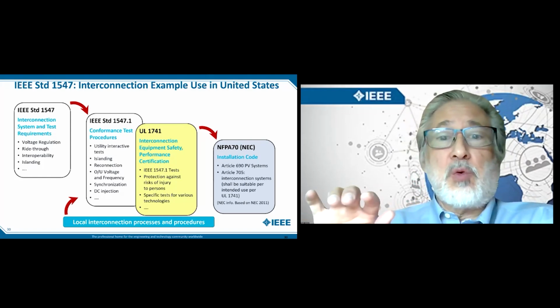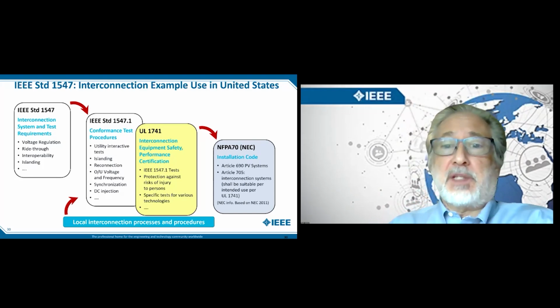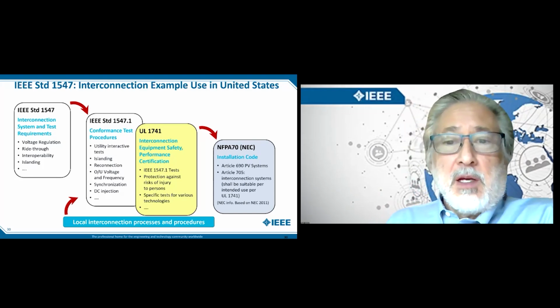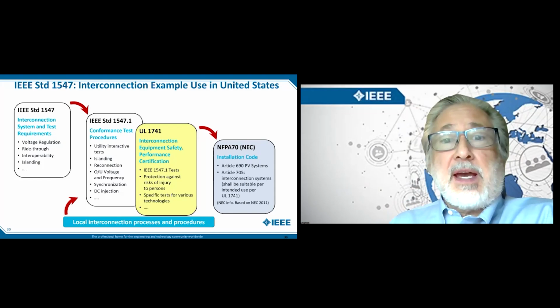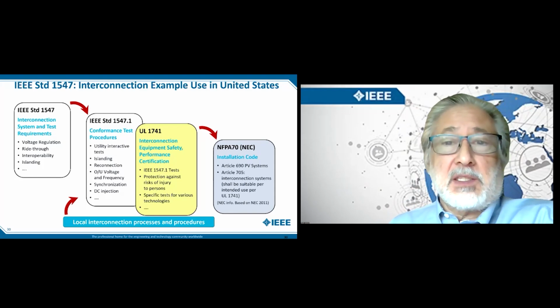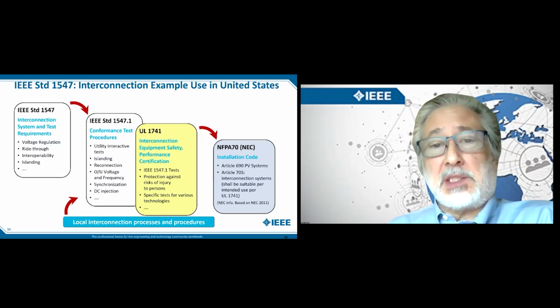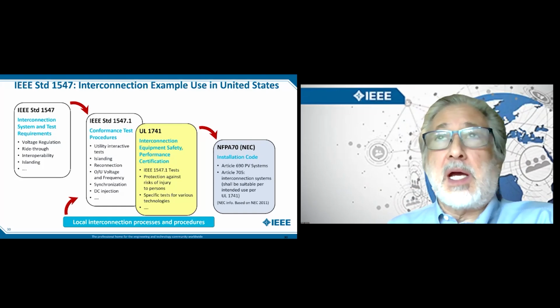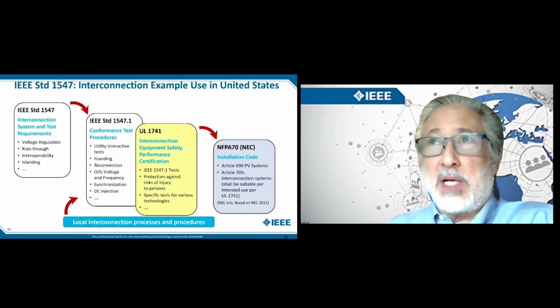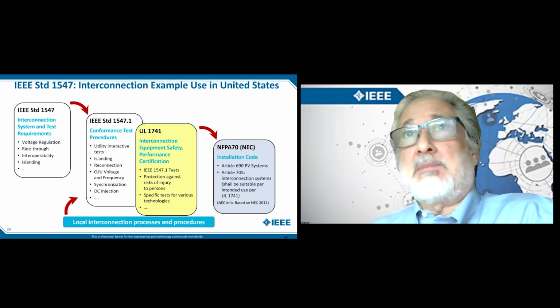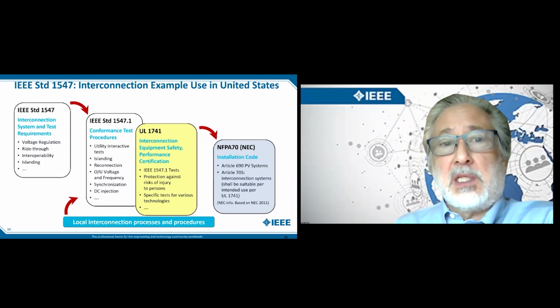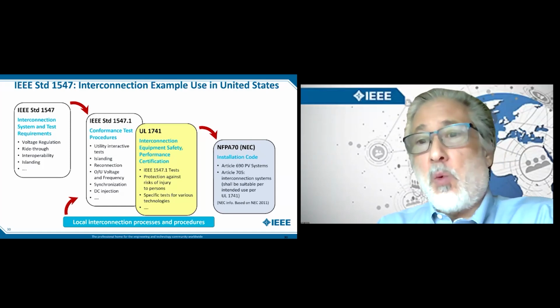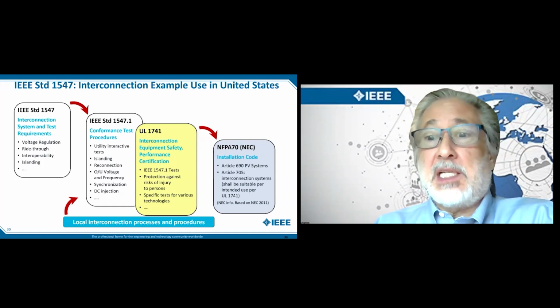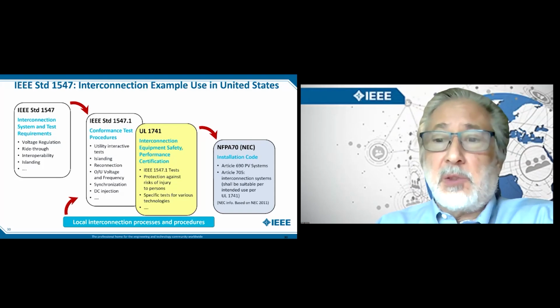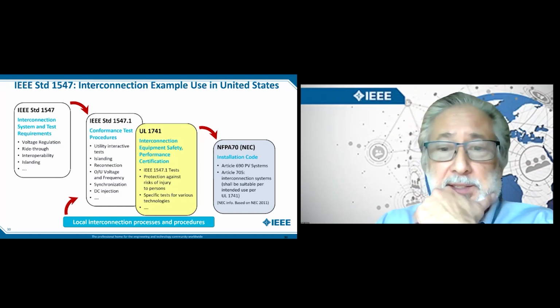More closely tied to 1547, UL has a certification that tests and certifies that devices and systems — products essentially — are 1547 compliant. Where this comes up most in practice is the certification of inverters to UL 1741, and the NEC does cite and call out UL 1741 as well.